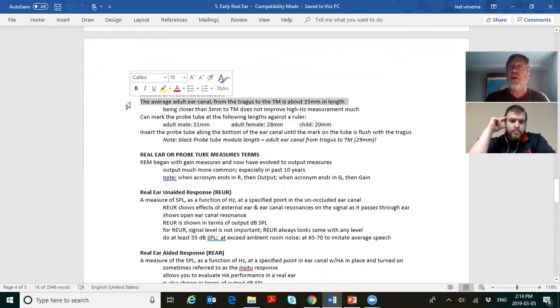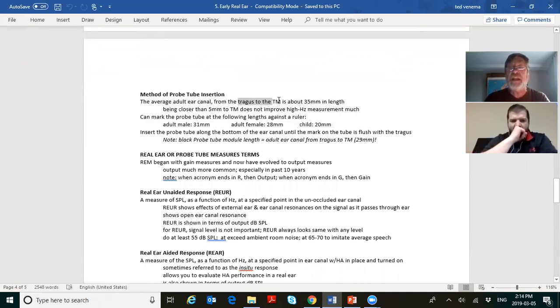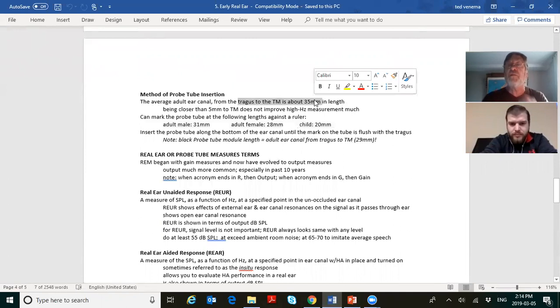30 centimeters, I should say 30 millimeters or 29 millimeters. Look what this says. From the tragus to the TM is about 35 millimeters in length. So if the black box is 29 to 30, that means that when the ring is placed 29 to 30 millimeters from the end, the tip of the tube will be 5 millimeters from the TM, because the length of the tragus to the TM is about 35.